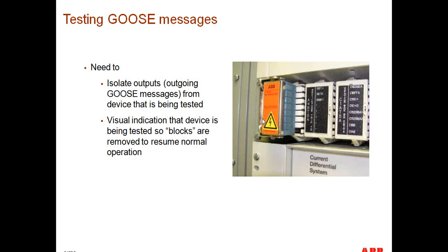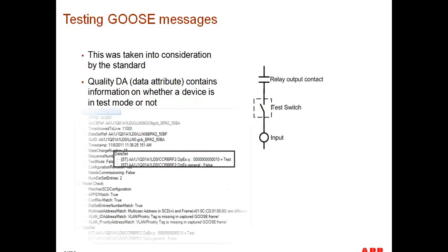And let's say if you're doing a reach test, or if you're doing a timing test, you can still monitor the output contact of your relay. And at the same time, you have pretty solid indication here that the device is being tested, so that this provides visual indication to field engineering that if the device is to resume normal operation, this needs to be removed. So how do we accomplish those two things with GOOSE messages?